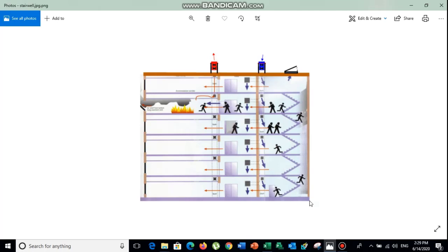First I will explain the stairwell pressurization system, and after this I will show you how to calculate the required airflow to pressurize the stairwell. As you can see, when the occupied space catches fire, smoke will flow toward the stairwell. We need to pressurize the stairwell so that smoke will not enter it, and instead is pushed back toward the occupied space.